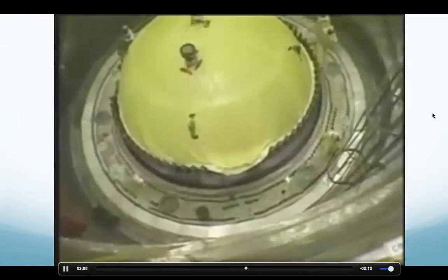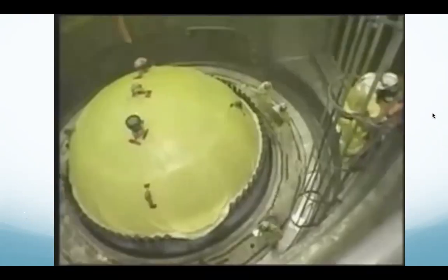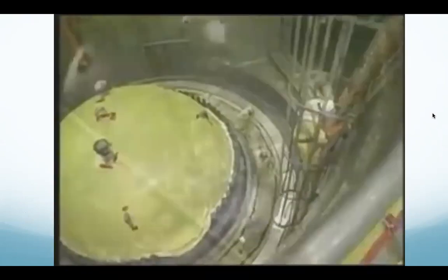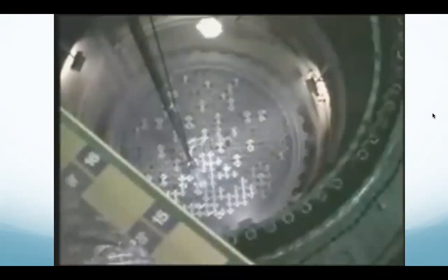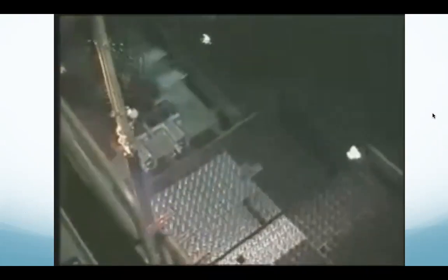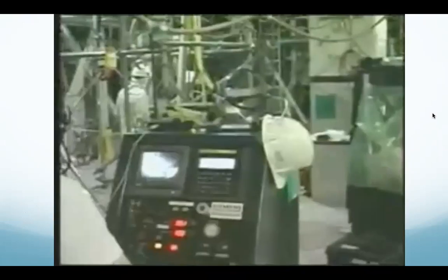But during the refueling outage, this entire floor is transformed into a strictly controlled and highly choreographed work area. We remove the layers of shielding and various components from inside the reactor vessel, then flood the open cavity with water. Using very detailed procedures, operators move old fuel, called spent fuel, into the spent fuel pool and move new fuel into the reactor. The outage is also an opportunity to do maintenance and upgrades on other equipment that isn't accessible when the plant is operating.